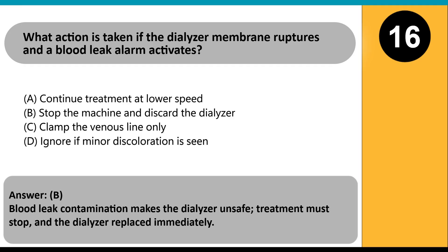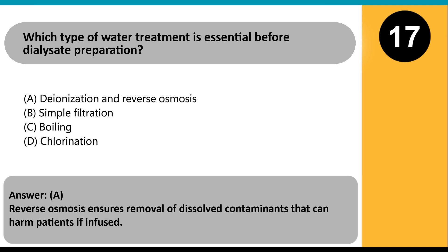What action is taken if the dialyzer membrane ruptures and a blood leak alarm activates? A. Continue treatment at lower speed. B. Stop the machine and discard the dialyzer. C. Clamp the venous line only. D. Ignore if minor discoloration is seen. Answer B. Blood leak contamination makes the dialyzer unsafe; treatment must stop and the dialyzer replaced immediately. Which type of water treatment is essential before dialysate preparation? A. Deionization and reverse osmosis. B. Simple filtration. C. Boiling. D. Chlorination. Answer A. Reverse osmosis ensures removal of dissolved contaminants that can harm patients if infused.